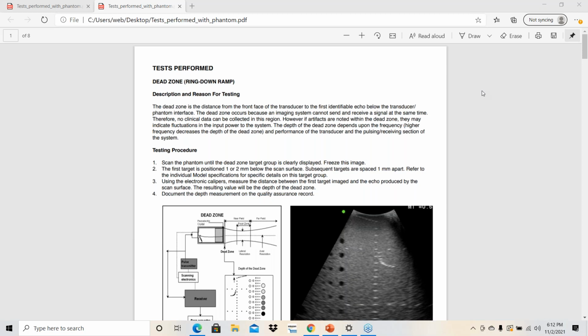And it tells you the testing procedure. Scan the phantom until the dead zone target group is clearly displayed. That's that target group at an angle. So it clearly, it's in English. There's no physicist language. First target is positioned 1 or 2 millimeters below the scan surface. So you just want to make a measurement from the top of the image to the first one you can see. It's a caliper measurement. It's not hard to do. Use the electronic calipers and document the measurement. So super simple. Okay, that's test 1, and then it goes on further.